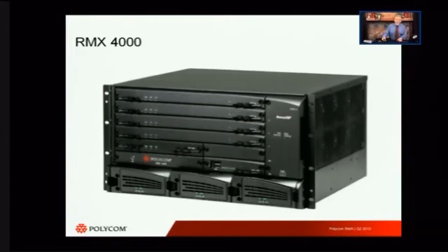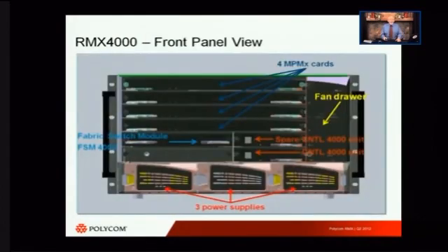Last but not least is the big brother. This is the RMX 4000. As you can see, he's a pretty big guy. He really is. He weighs in at a whopping, if he's fully loaded, somewhere near 85 pounds. So don't try to load him or install him by yourself. You're going to need somebody to hold him up as you're putting the screws into the rack. Okay, I have done it by myself, but I kind of cheated. I stripped all the cards out of it and then held it up there. It doesn't weigh very much that way. But be careful. You probably need to have a good helper with you to do this.